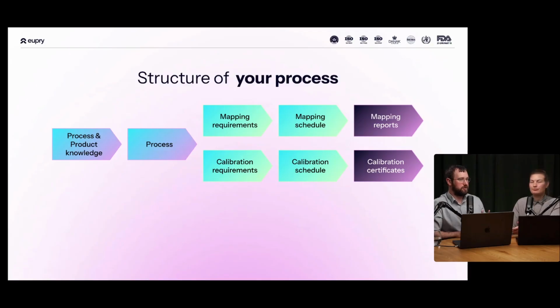And so, as we've talked about, if you know what your process is based on your products, then it's very easy to translate those into calibration requirements. Exactly. You know what your process is, what your desired temperature range is, then you know what your calibration points are, you know how much uncertainty you're allowed to have, and that means you know what your calibration schedule is. Yeah. And you know exactly what kind of documentation you need as well.